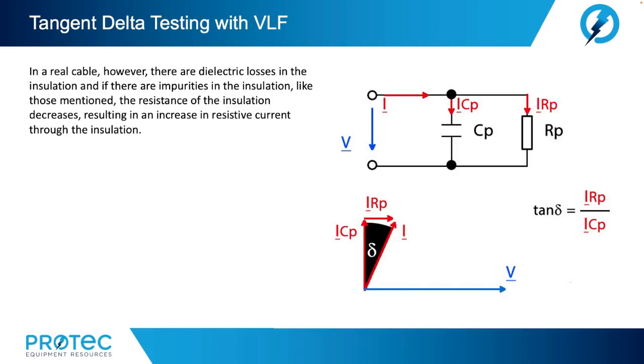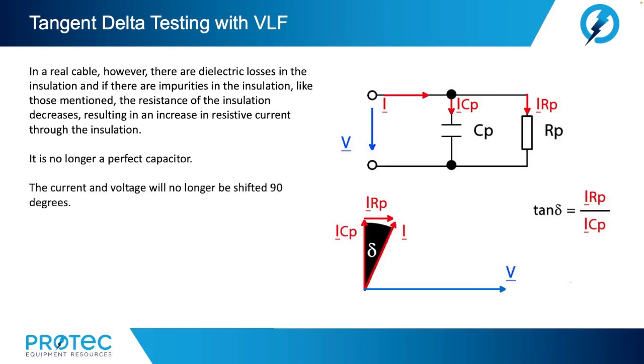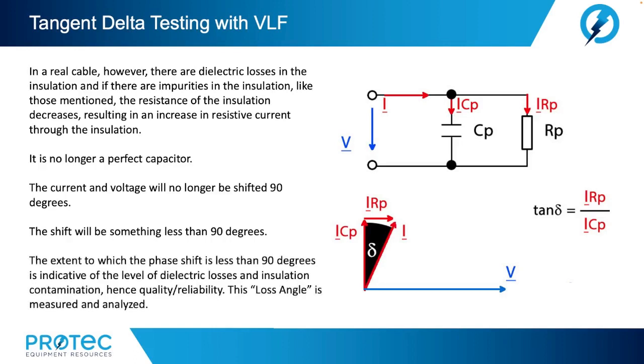In a real cable, however, there are dielectric losses in the insulation, and if there are impurities in the insulation, like those mentioned, the resistance of the insulation decreases, resulting in an increase in resistive current through the insulation. It is no longer a perfect capacitor. The current and voltage will no longer be phase shifted by 90 degrees. The shift will be something less than 90 degrees. The extent to which the phase shift is less than 90 degrees is indicative of the level of dielectric losses and insulation contamination, hence quality reliability. The loss angle is measured and analyzed.